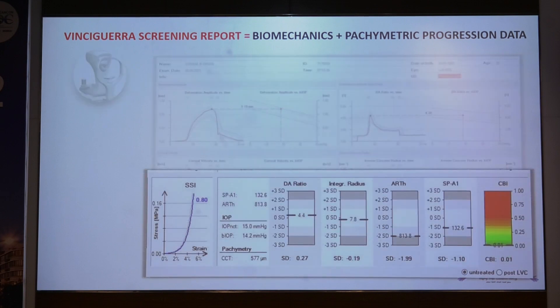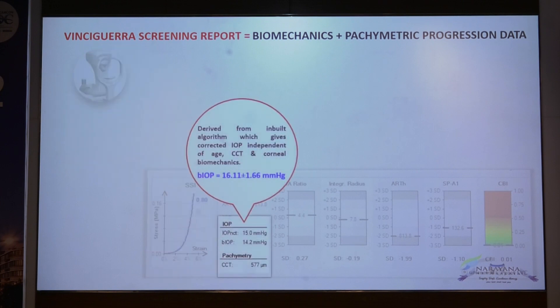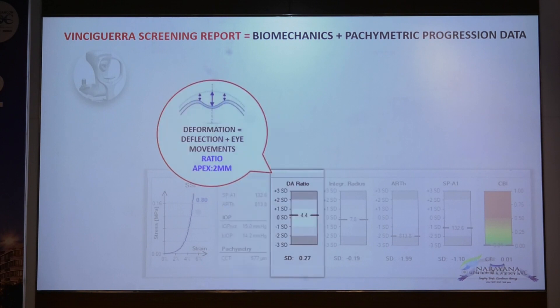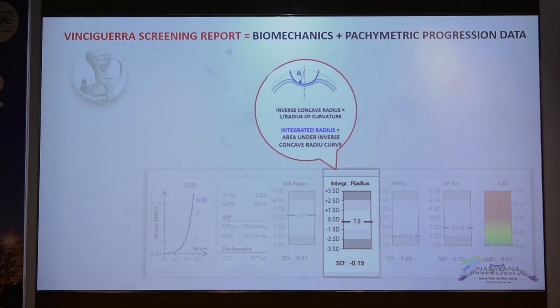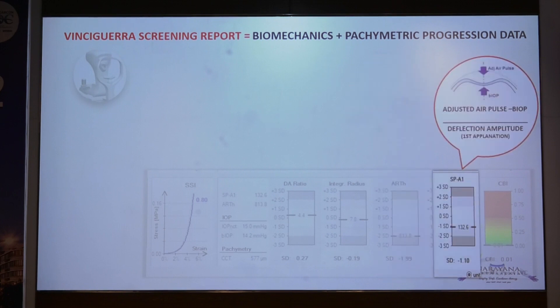The Vinciguerra screening report includes the SSI curve, which shows the intrinsic elastic properties of the cornea — normally equal to 1; less than 1 indicates a softer cornea, more than 1 a stiffer cornea. The bIOP is extremely important because it is the biomechanically corrected IOP, independent of age, corneal thickness, and corneal biomechanics. The deformation ratio includes both deflection and eye movements due to the air puff. The integrated radius is the area under the inverse concave radius curve — the more the area, the softer the cornea. The Ambrósio relational thickness to the horizontal profile includes pachymetric thickness divided by pachymetric progression. The stiffness parameter is the adjusted air pulse minus bIOP, divided by the deflection amplitude — the higher the value, the better the stiffness and biomechanics.